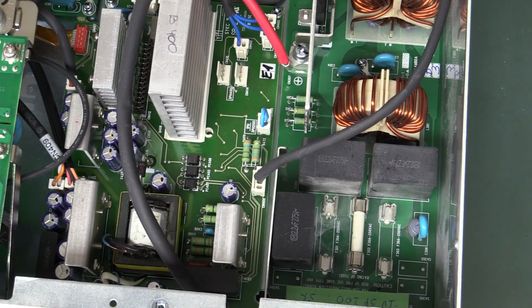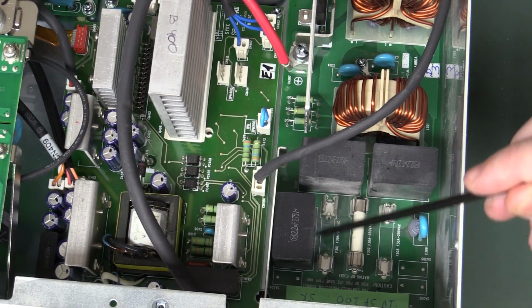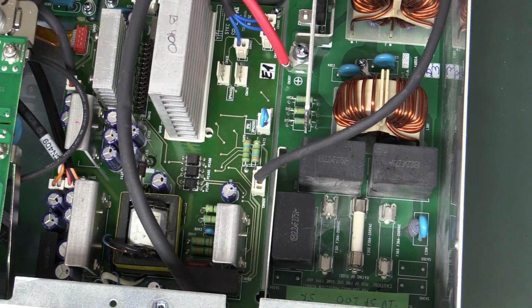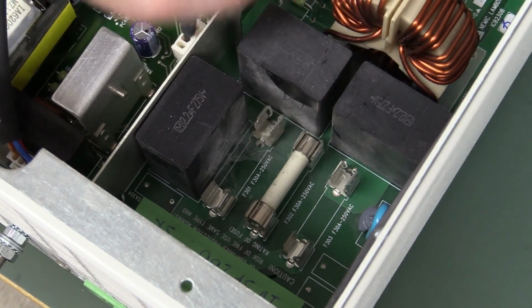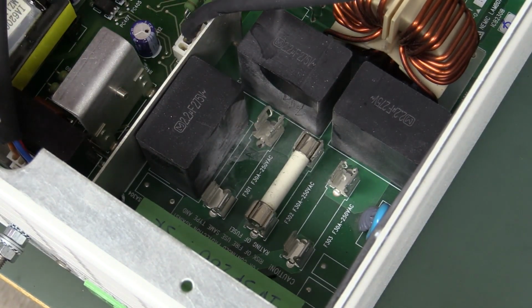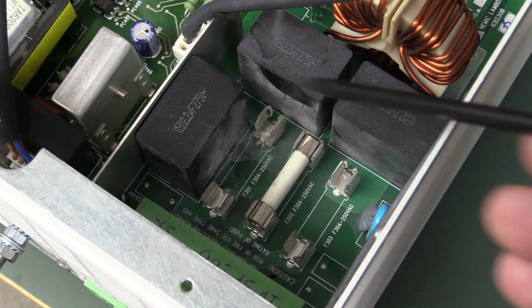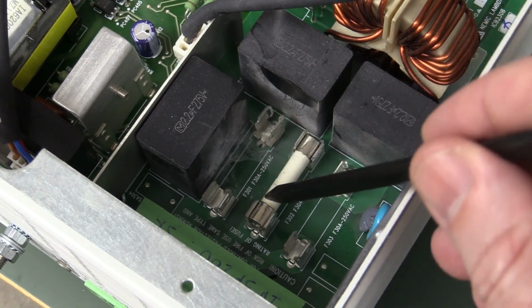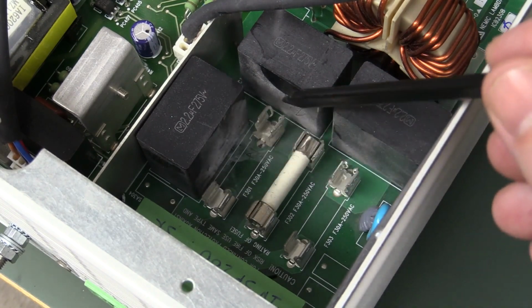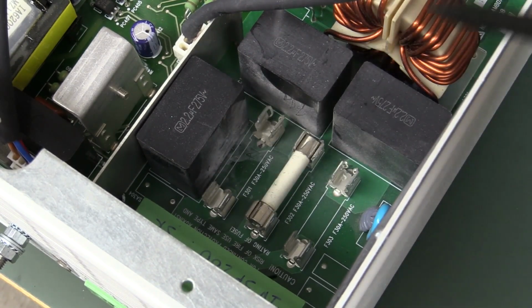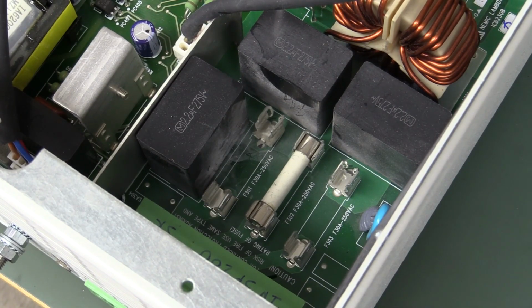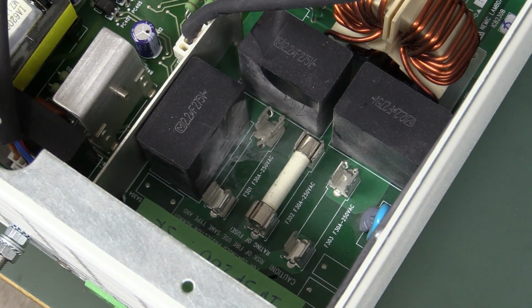They're missing, so I don't know whether somebody's had a go at this thing, or whether the fuses just blew out. I mean, look, something's happened there, perhaps. Yes, actually, if you see, on the side of these caps here, look at all that. There's all this crud. I mean, this is a very clean unit. This crud is not anywhere else. It's not dust or anything like that. So it looks like this fuse here has likely totally exploded, and all the crap, it's not charred everywhere, but, I don't know, has the ceramic exploded? I don't know, but HRC fuses are supposed to take huge surge currents like that, so I'm surprised I can't immediately see anything else visually blowing in this thing.